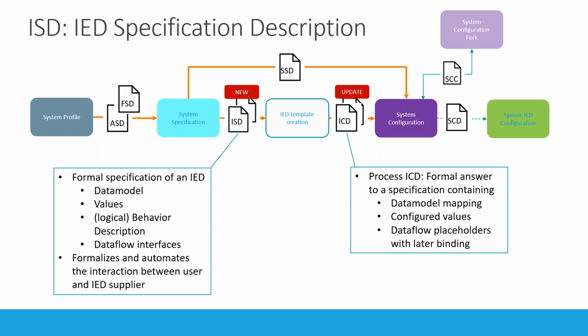So it contains all the necessary elements to tell a user how the IED supplier has implemented what you specified — whether the data model conforms to his device, whether the values you specified are implemented, and whether the data flow placeholders in your specification are implemented inside the real device. This is a very efficient way of working, and the process ICD also allows you to automate the validation step on the user's side to validate what you received from an IED supplier.